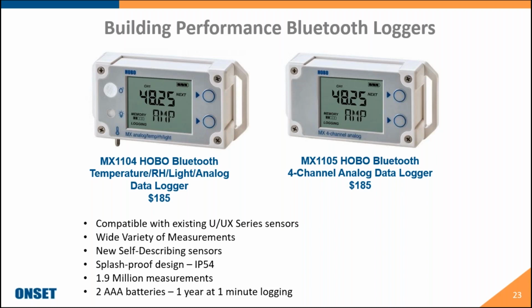These data loggers will give you a wide variety of measurements that you can record. We did release a new suite of self-describing sensors for them, and they do have an IP54 rating, which means that they are splash proof. These data loggers have a lot of memory in them, and they can basically store up to 1.9 million measurements before the memory fills up. And they operate on just 2 standard AAA batteries, and you should expect about a year's life out of those at a 1 minute or greater logging interval.